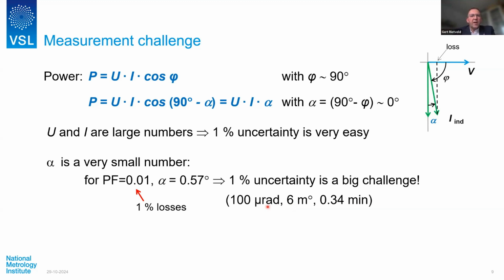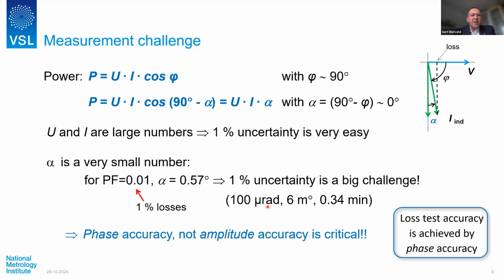As Ilya already indicated, in energy metering, phase doesn't come in, it's all about magnitude, but here it's all about phase, and the phase requirement is really stringent. So that is, I would say, one of the key messages of my presentation. In loss measurements, it's all about phase accuracy, and you can only achieve high accuracy and good reliability in the loss measurement if you have a low phase error. So effectively, this transformer loss measurement equipment is designed to have a very low phase error.